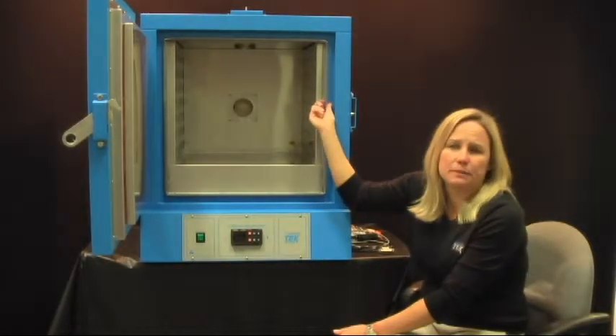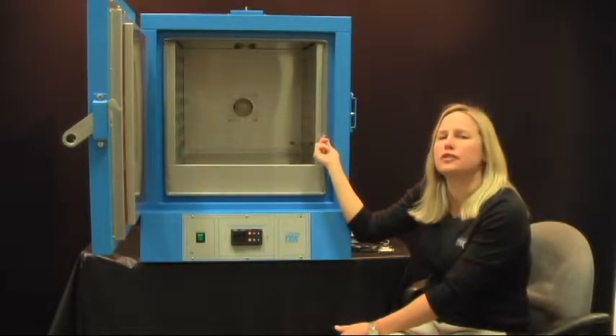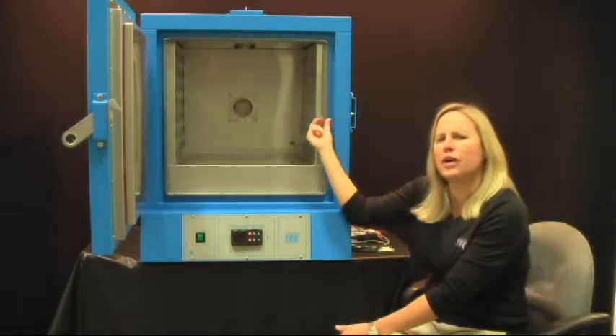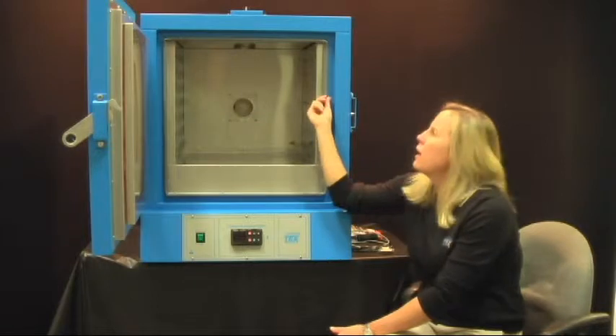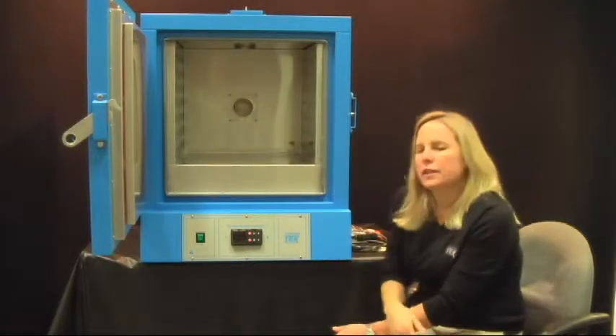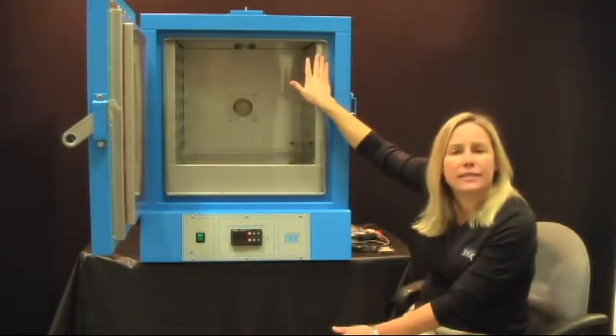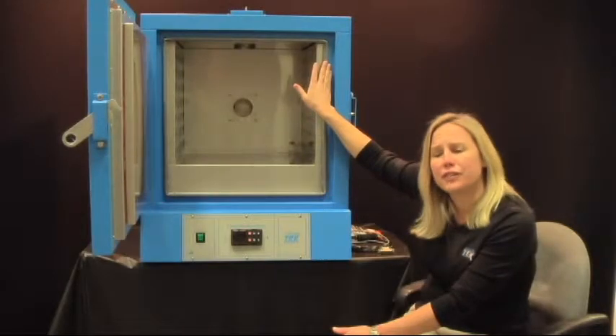This door gasket here is really only comfortable with about 235 degrees C. Is that right, Catherine? That's right. It's silicone. So, the oven will come with a door gasket that can take about 235 degrees C.